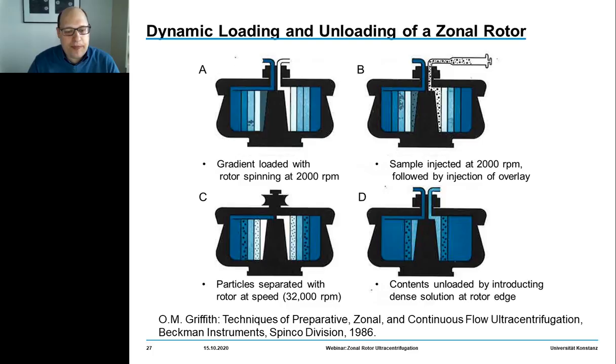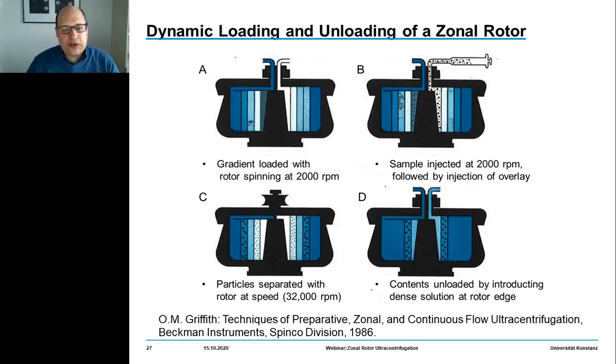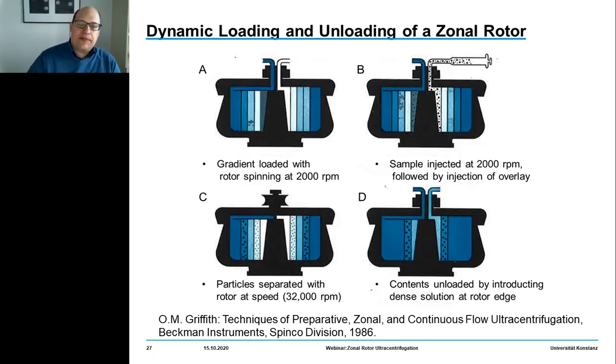Once the nanoparticles are properly banded into discrete zones for the different particle populations, we decelerate the rotor back to 2000 RPM, remount the two-way fluid seal, and harvest the zones of banded particles by pumping in a very dense solution of gradient material towards the rotor edge, displacing the zones of banded particles via the center line.